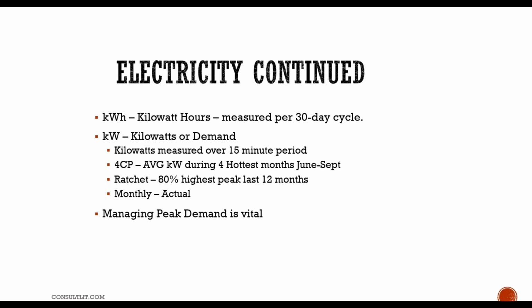For that moment of time, because every motor is starting up, every light is kicking on, every ballast, the amount of energy it takes to start everything is going to spike. And that moment in time, that 15 minutes on a Sunday morning, that high spike, which is unusual because we typically don't need the whole building the rest of the week, that's setting what the utility company is charging us for our kilowatt hour usage. Am I saying that right? Okay. And so that's the difference, where that moment of demand is setting the price for our usage for the rest of the month or the rest of the year.